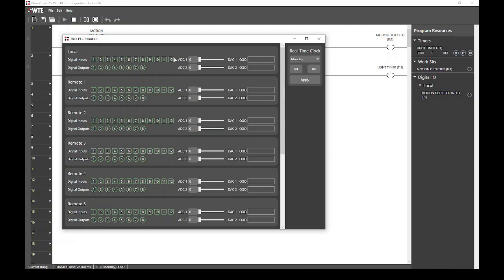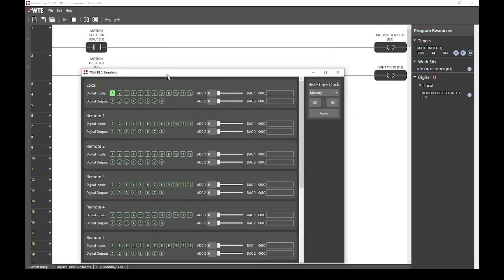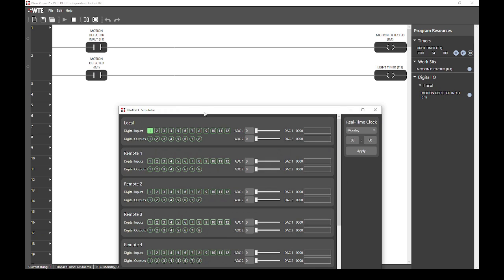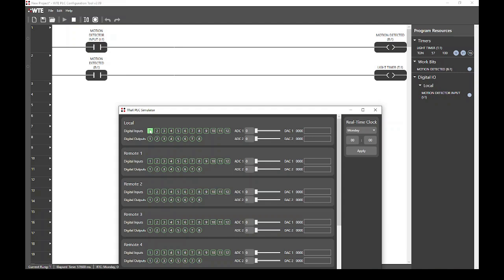On top, we can see the digital inputs, and on the bottom, we can see the digital outputs. We can enable digital input 1 by clicking it. Now we can see that timer 1 is running under the program resources pane on the right hand side. Currently, this timer will only operate while input 1 is closed. We want the timer to continue to operate even after input 1 opens again, and we can do this by latching the timer.